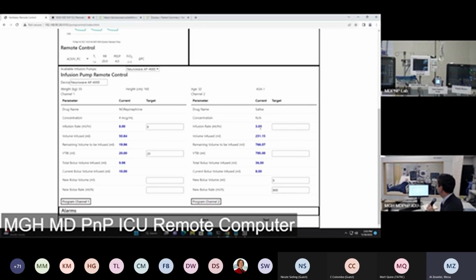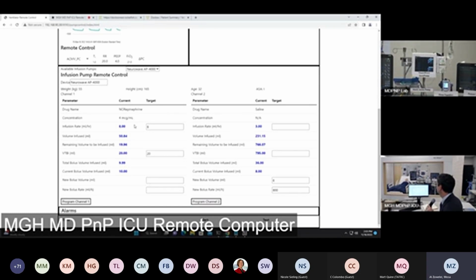We use those to build a set of required or necessary or desirable communications elements from the pumps, things that we wanted to be able to read from the pumps or control remotely. And we compiled those in a medical device information data sheet, or MDIDs, for controllable pumps. So the NeuroWave does the best job of implementing all of these. It basically covers everything that we would want from the MDIDs. And we can see that we get the drug name, we see the concentration of the drug, current values for a lot of different settings. And we're able to remotely set those, and we're able to read that information from the pump.